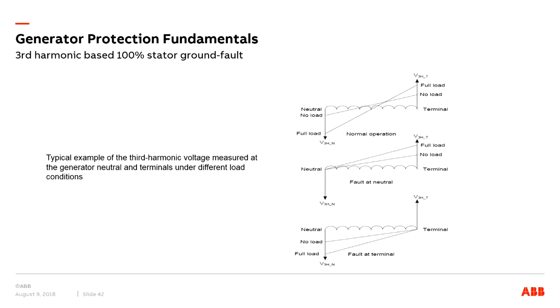So here is how third harmonic content looks in the different operating situations. In normal operation, you have so much third harmonic, which is equal from both sides of the generator. When there is a fault at the neutral, then the third harmonic content reduces or falls on the neutral side. And when there's a fault at the terminal, it happens the other way. So this is a good way to detect the last 5% or protect the last 5% of the stator winding.